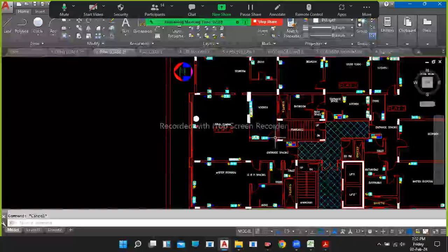Yes sir, as per the load balancing we did yesterday. For lighting it is 6 amps and 2.5 square mm cable. For raw power it is 4 square mm cable size and 16 amp circuit breaker.